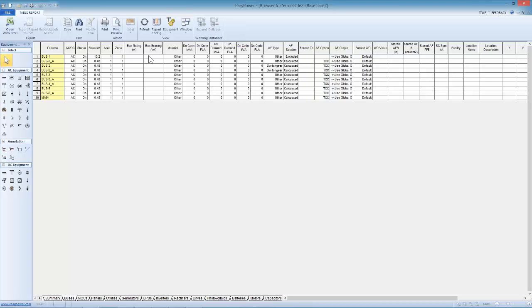For that purpose, we need to have listed the manufacturer's guaranteed rating for that piece of equipment. So just looking here at my bus listings, I can see I have a significant deficiency in the interrupt rating that may be listed on the equipment, may be part of the data sheet, but for some reason I didn't get that included when I was building my one-line diagram. Now when I go to some other elements, and right now I'm just going to touch on the cables and breakers, but the same applies to every element in the system.